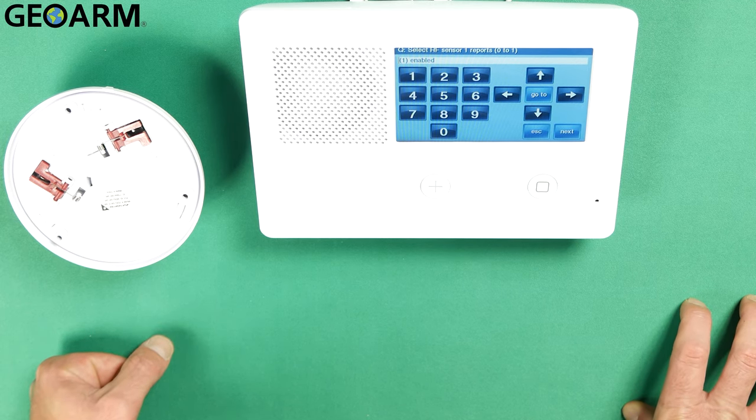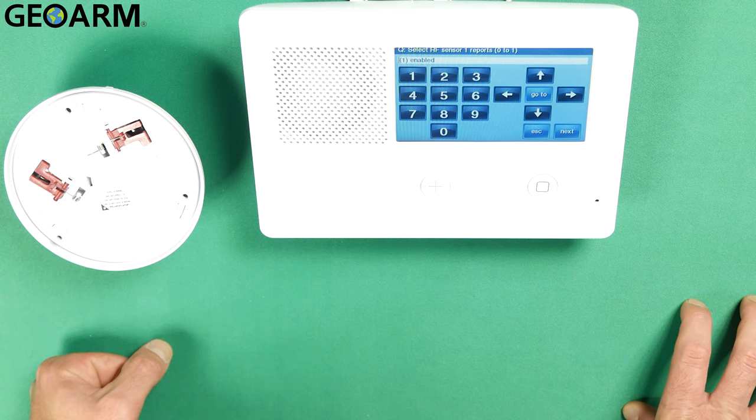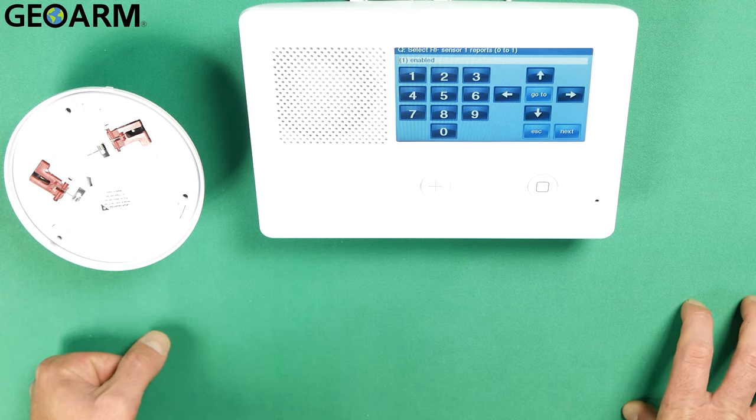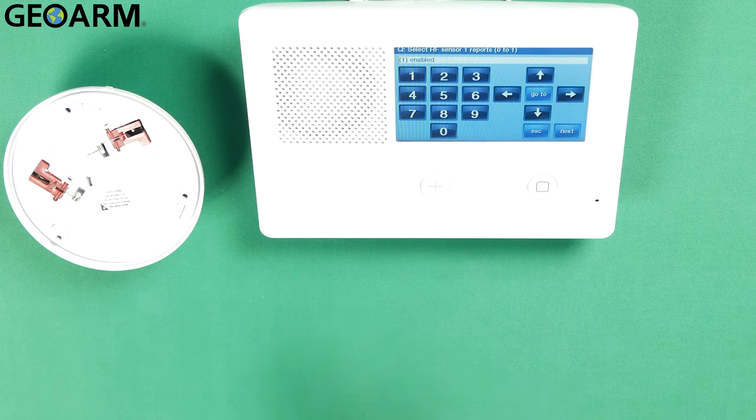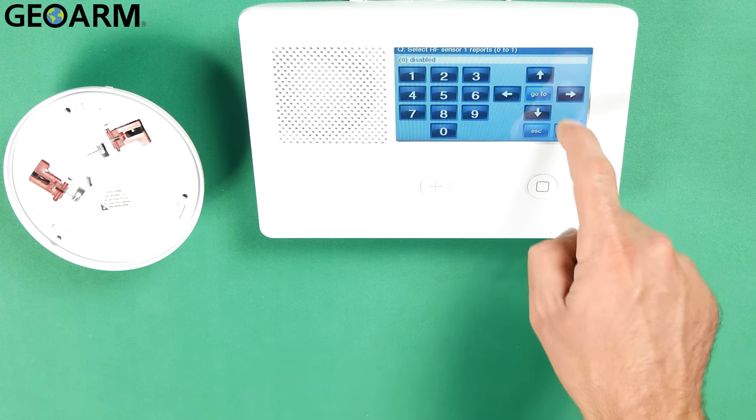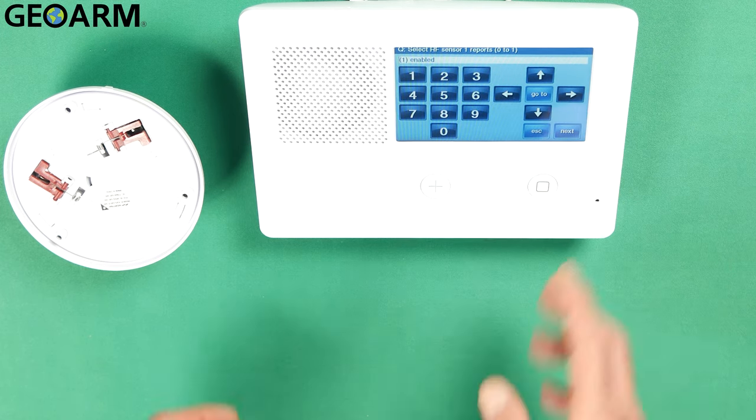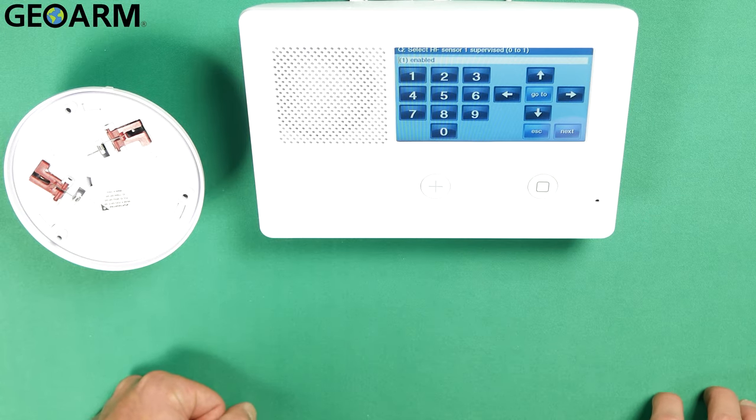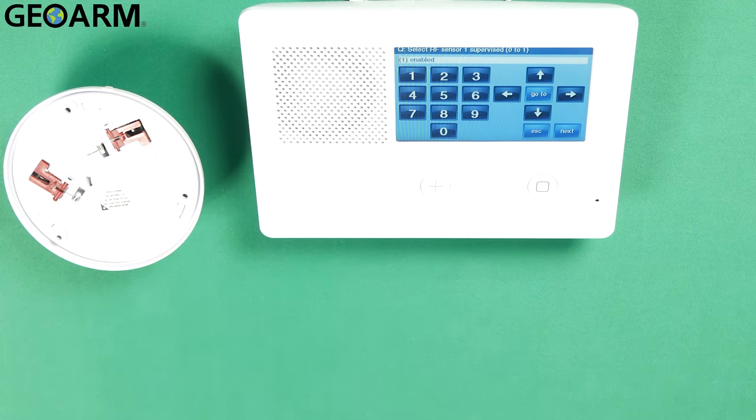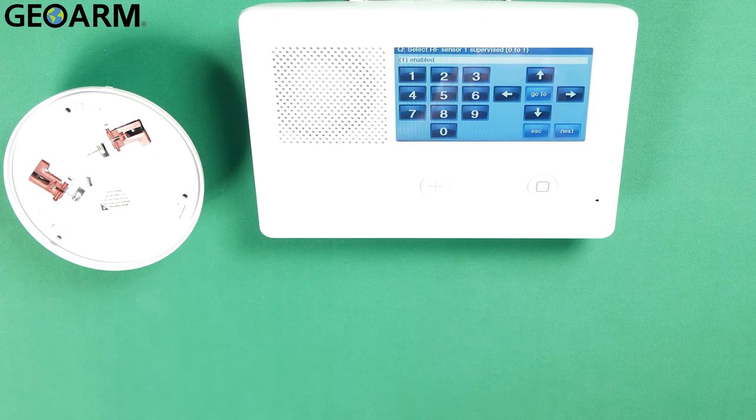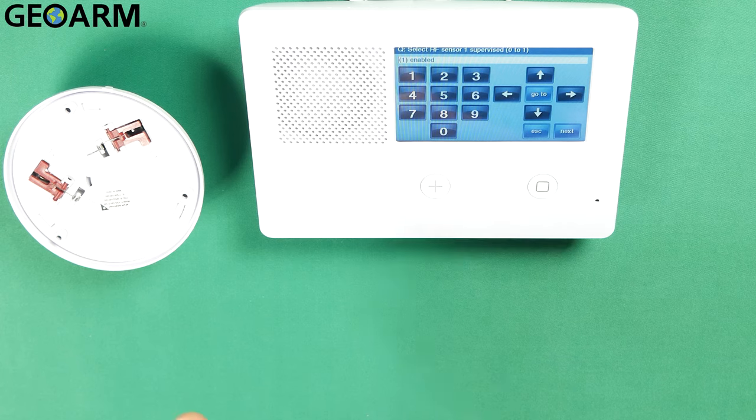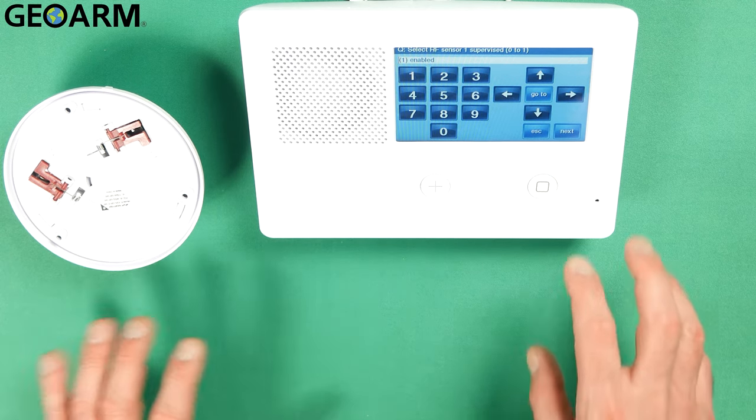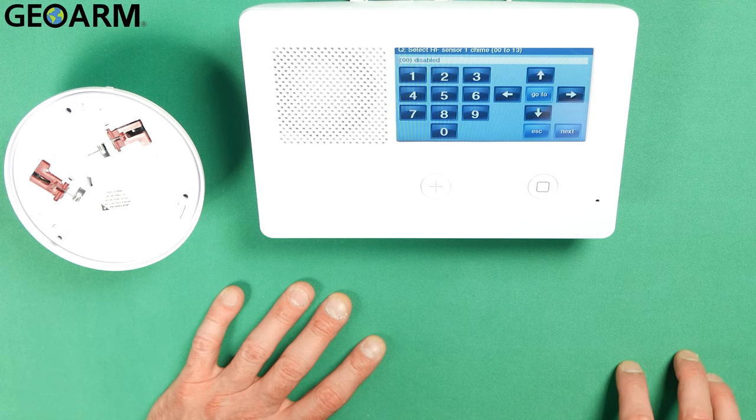Now it wants to know if it's going to report to the central station or not. I do want it to report to the central station. For those of you that want to set it up as a local only device you could press the right arrow to disable it. I don't want to. I'm going to leave it enabled. I'm going to press the down arrow at this point. It wants to know if this sensor is supervised for this field. We do want it supervised because it's going to report whenever it has a low battery condition. It's not getting back to the panel. That kind of thing. So supervision you definitely want. We're going to leave that enabled and press the down arrow.